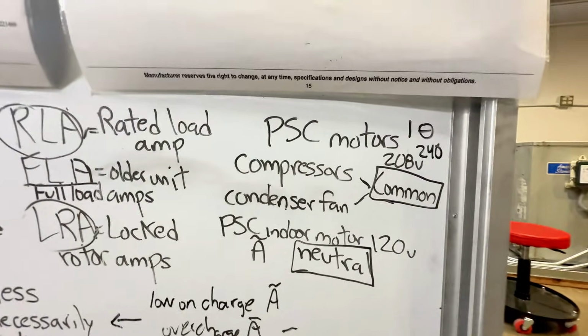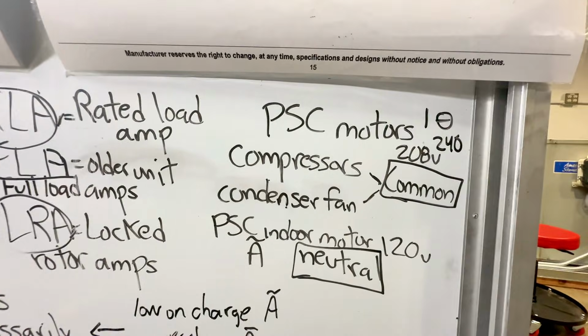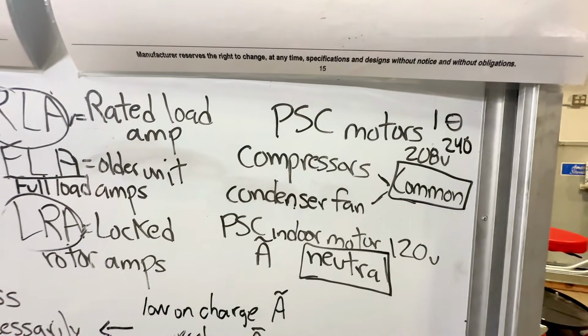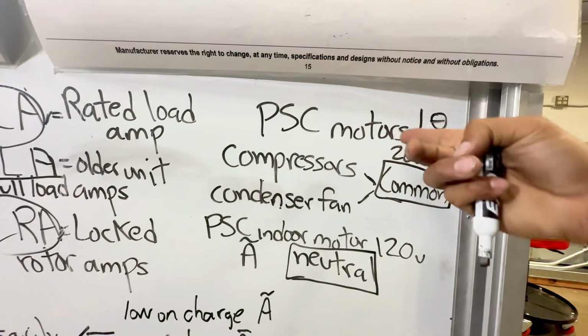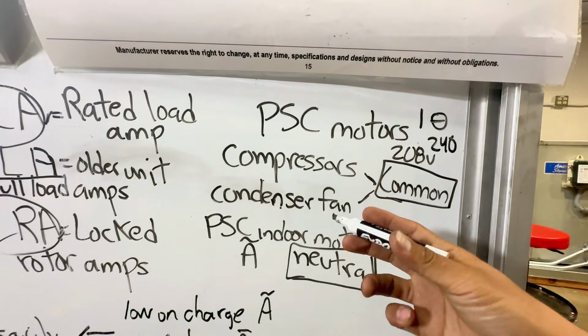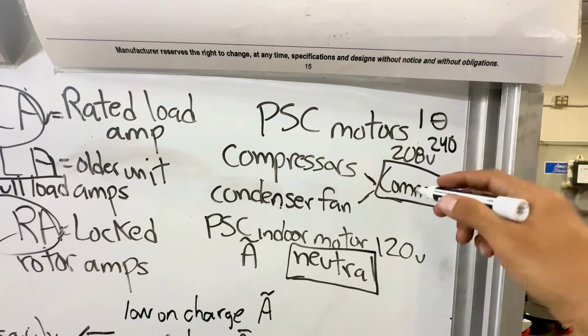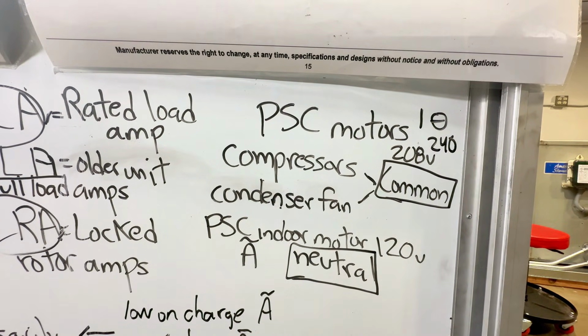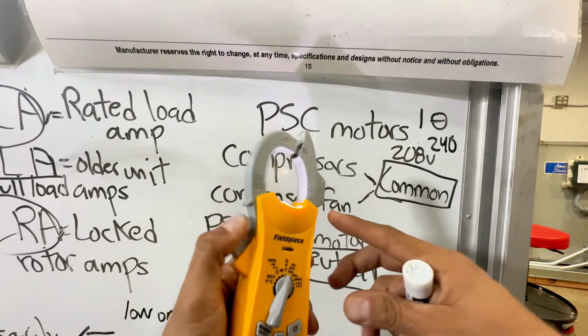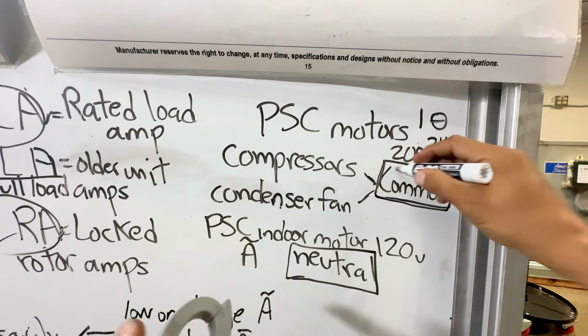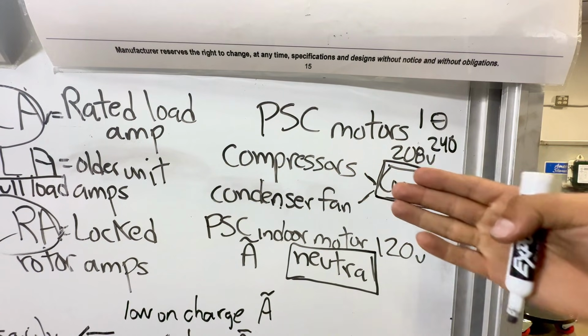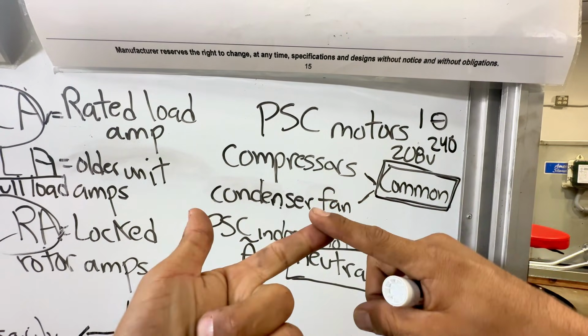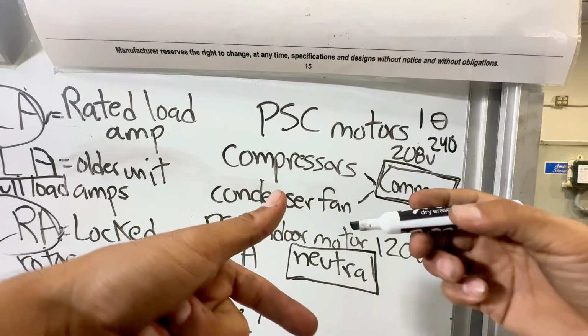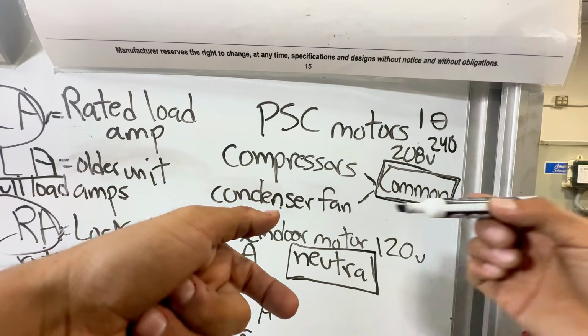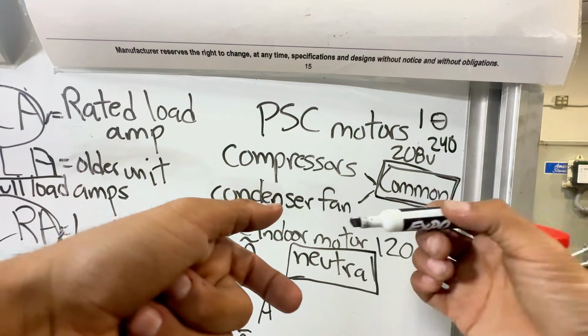And this is where I got confused for a second when I started off in the field. When you're dealing with permanent split capacitor motors, right? Your compressor, your condenser fan motors that take a capacitor, you're gonna put your meter and check amp draw on your common. If you remember, compressors and condenser fan motors have a run winding and a start winding. But the thing that they share in common is your common. So you're gonna check your common for amp draw. That's gonna give you the true number for your amp draw.